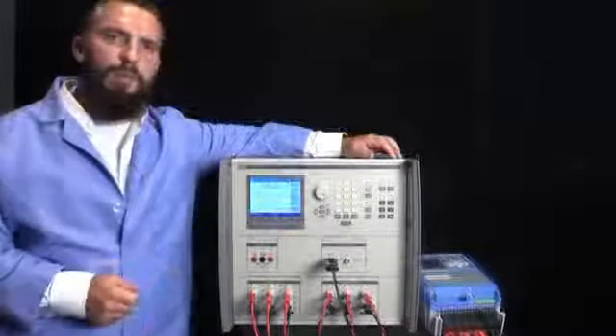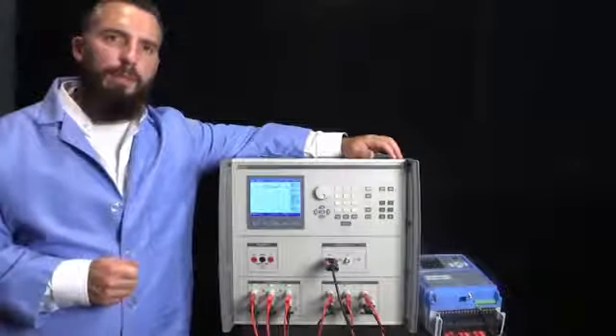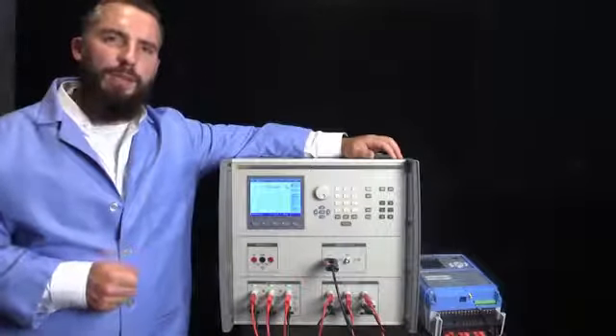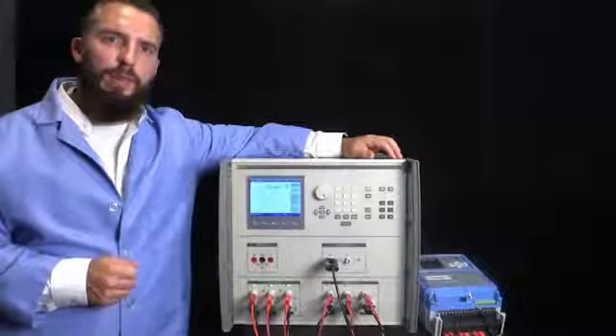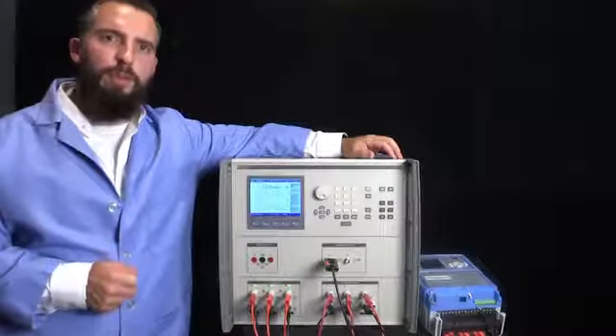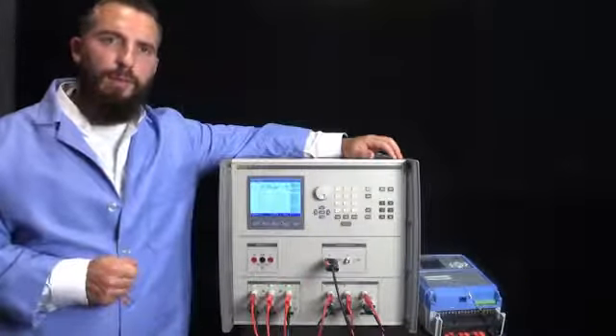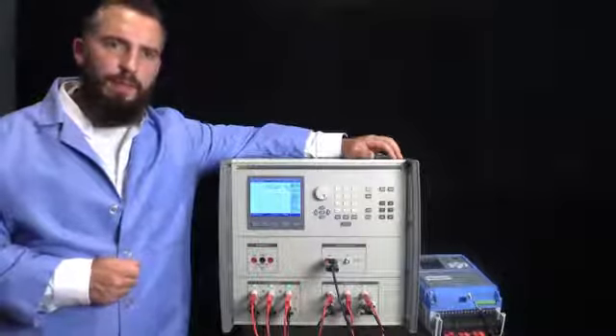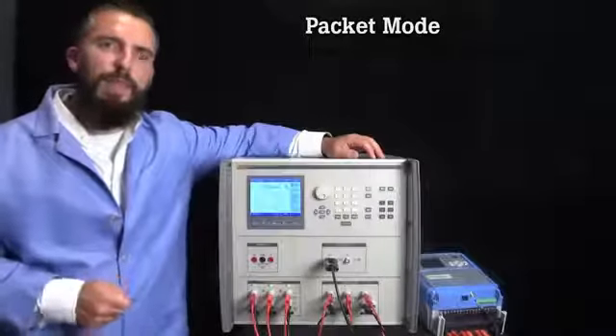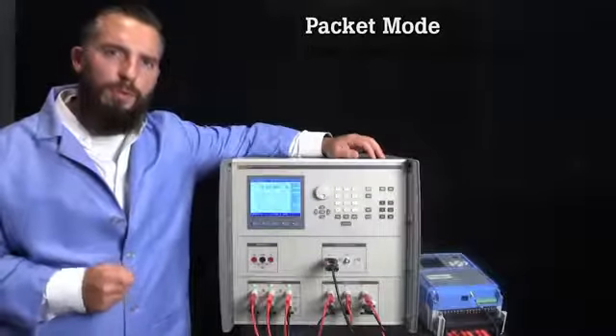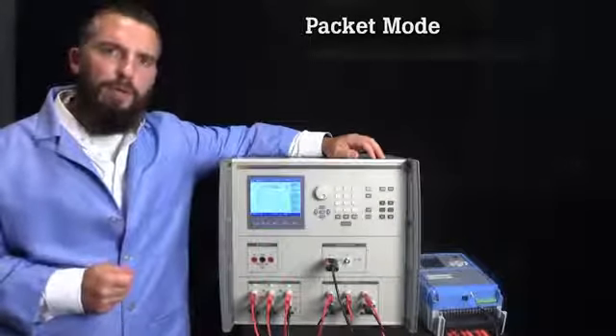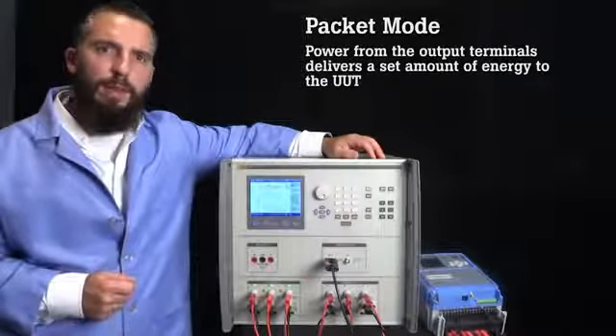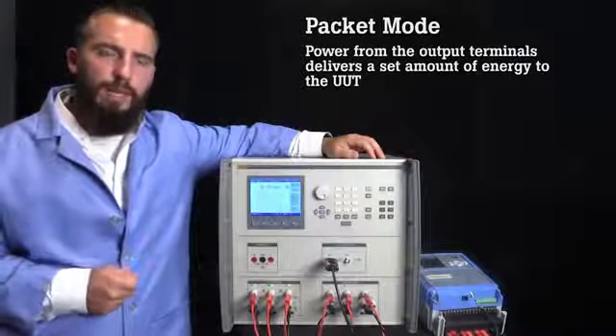In some cases, you may have to test an energy meter without a pulse output. In this case, the simplest method is to do a timed energy test where you compare the expected value to the measured value on the energy meter. This can be done using the packet mode. In packet mode, which is also known as dose mode, the power from the output terminals is timed to deliver a set amount of energy to the meter under test.